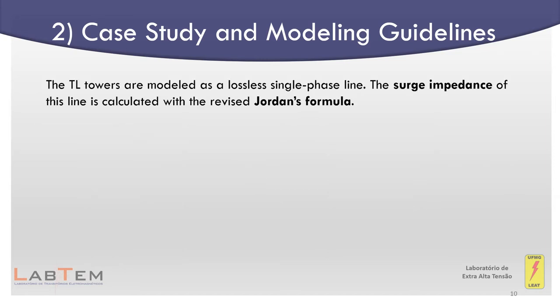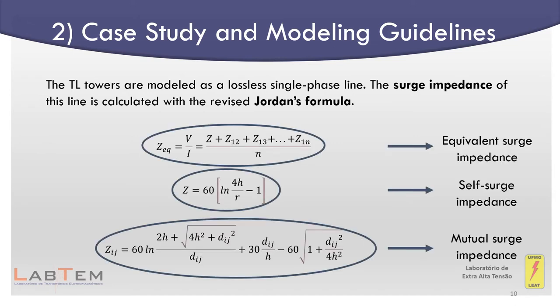The transmission line towers are modeled as a lossless single-phase line. The surge impedance of this line is calculated with the revised Jordan's formula. Considering that the tower can be represented by N vertical conductors connected at the current injection point, it is possible to represent the whole multi-conductor system as a single transmission line with an equivalent surge impedance given by the formula.